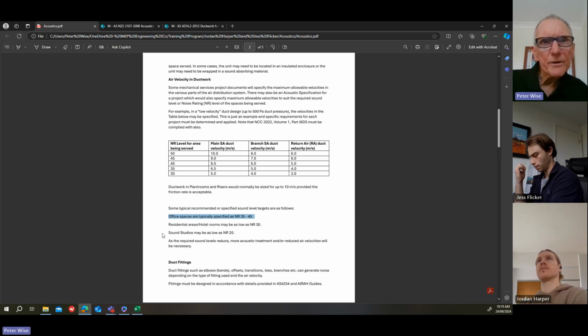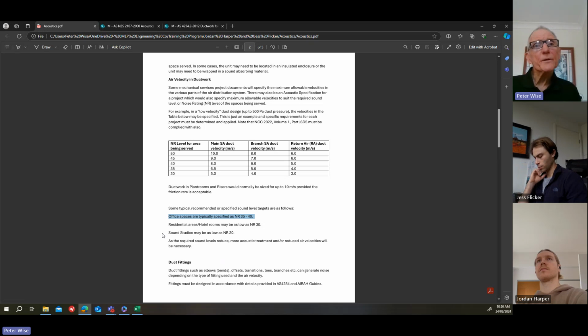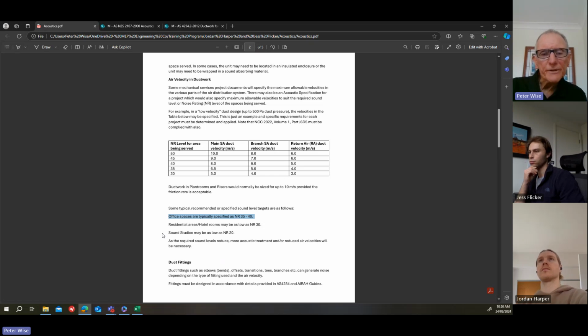If you're doing a film studio or sound studio, they'll have stringent requirements, and that's when you need to look at it closely. For a project like that, there would normally be an acoustic consultant who dictates what they want - the velocities in the ductwork, the sound levels in the space. They might even give you design information on how to design the system. If that's part of the documents, that's what you need to follow.